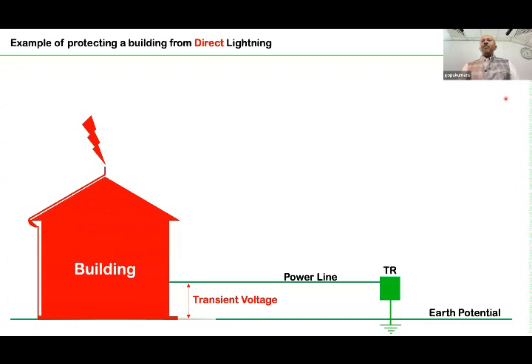Now, first of all, you have to make an equipotential bonding in your building in such a way that the entire building is at the same potential. All the metallic parts of your building are at the same potential. So a very good equipotential bonding is made. As a result, the whole building is red. Within the building, there is no damage because everywhere is zero potential. Now, where do you expect the potential difference? The potential differences can be expected between the earth, meaning that particular building, and all metallic services connected to the building. Say, for example, the power line. The power line, line and neutral, is at a totally different potential. The reference of line and neutral is the neutral earthing of the transformer. So it is at a different potential with respect to the building.